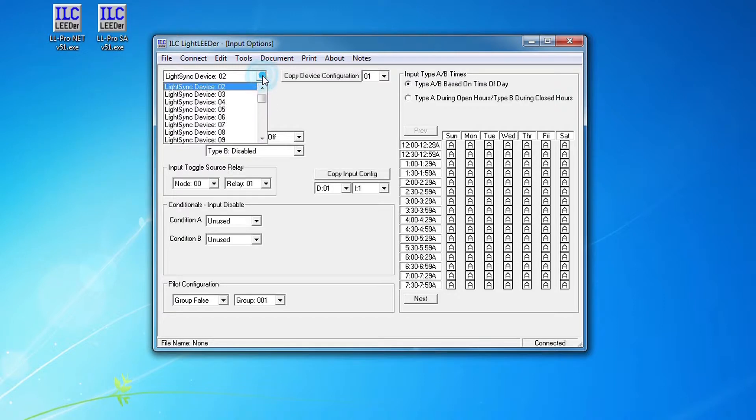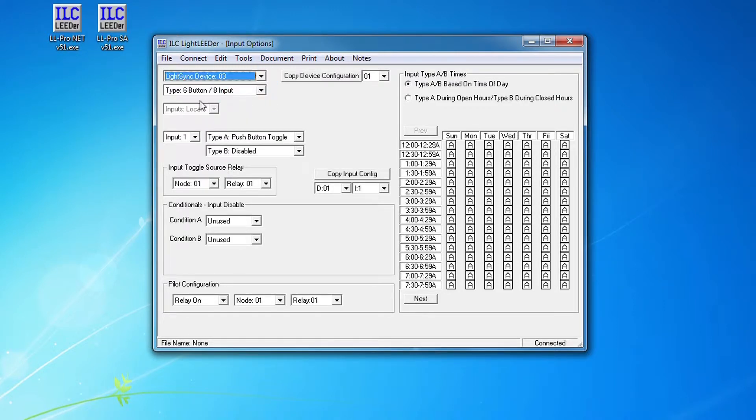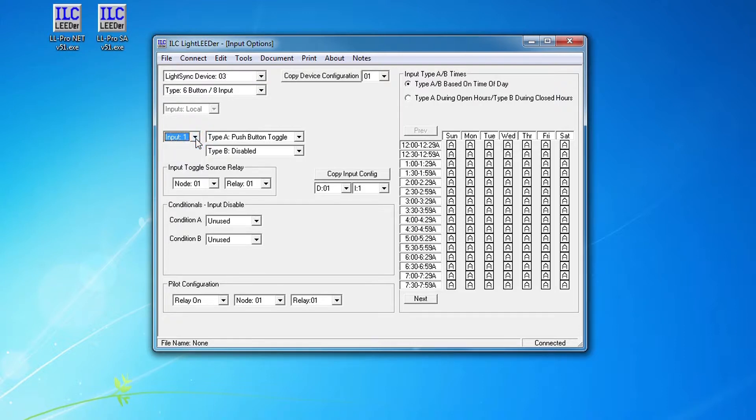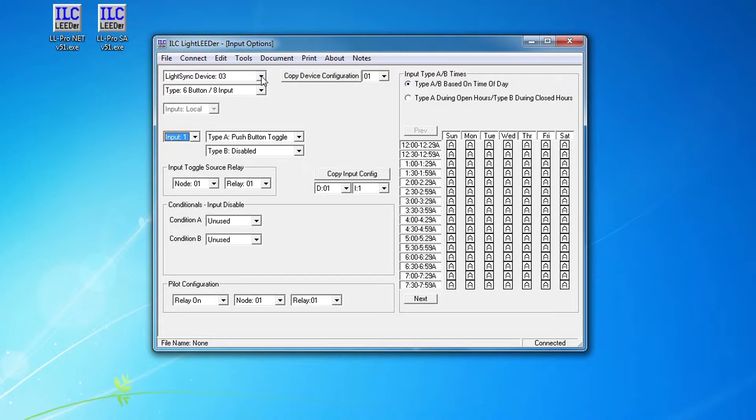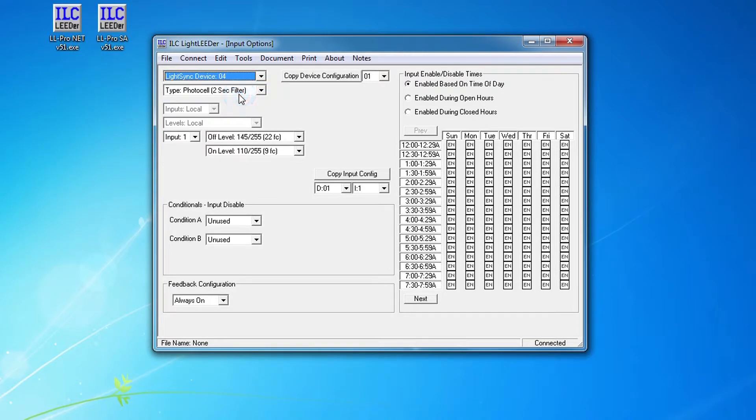If I go to my light sync device 03, that was a six button station so I could go here and cursor down through my six switches and see that they're all push button toggles on/off controlling the six different relays. I can go to my device four and I have that as a photo cell I had set for a two second filter because I was doing some testing.